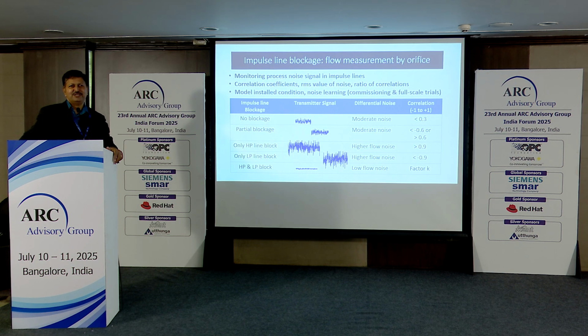In many situations, like in gas flow, the liquid condensate in the impulse tubes prevents an accurate measurement, or vice versa, you have gas formation or bubbles in the impulse tube, which could impact your measurement. Now, this is a very common scenario all around, and we did an experimental study, worth about 6 to 8 months, way back in 2004.